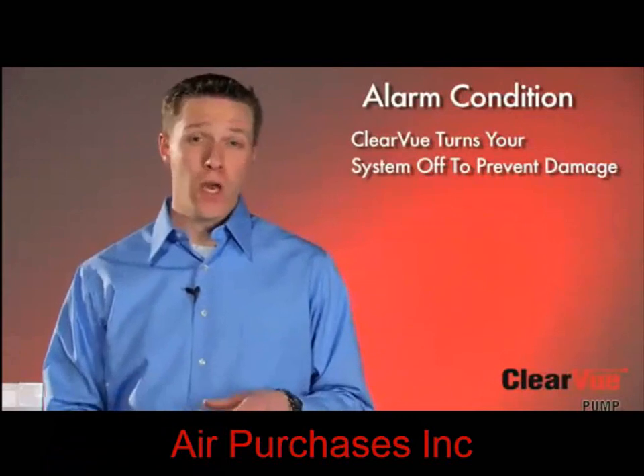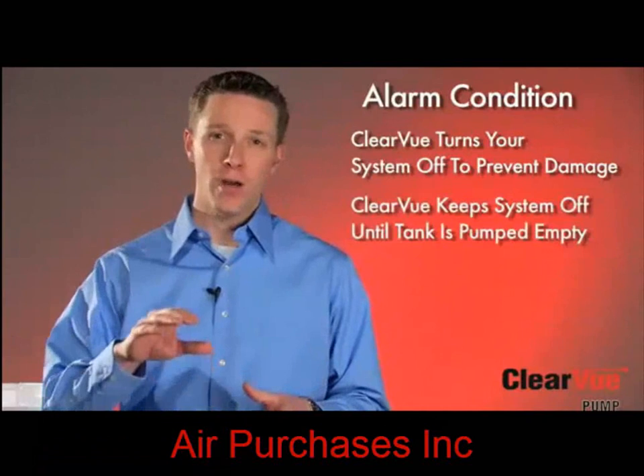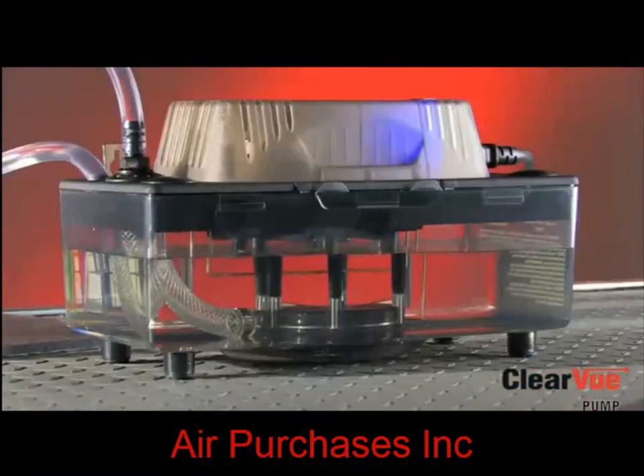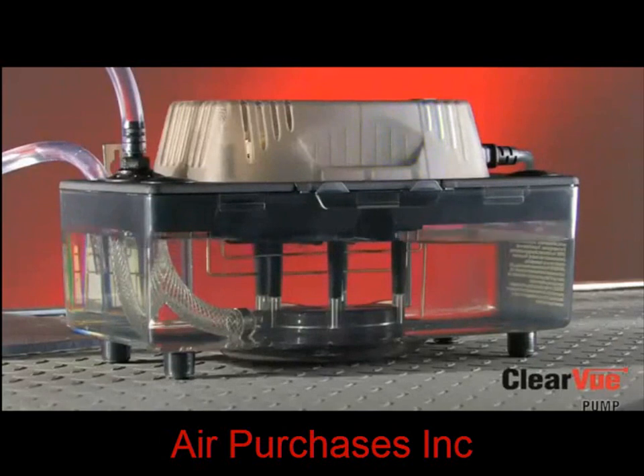The key difference between ClearVue and a normal condensate pump is that it will keep your compressor shut off until water has pumped down to the bottom of the tank and come off of that empty sensor. You may wonder why that's key. Water is sloshing back and forth in the tank during a clog. If your pump has a mechanical float, it will bounce up and down as the water sloshes in the tank, turning that alarm signal off, on, off, on. This will happen in any condensate pump with a mechanical float. This off/on alarm cycle will then short cycle your compressor, which we know can cause damage. Again, no float, no problem.